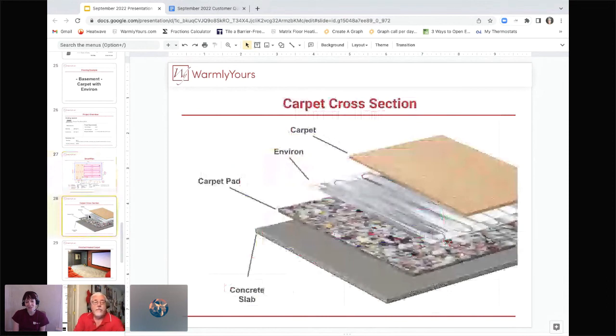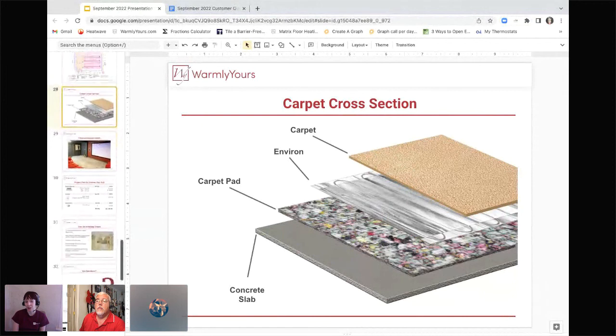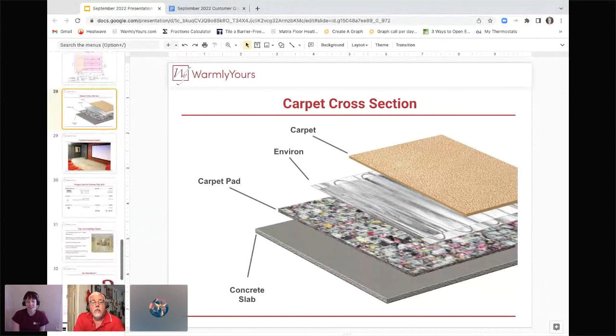Since we're doing carpet and using a carpet pad, we are forgoing the Cerazorb — the carpet pad itself serves as the thermal break. You would just lay the carpet pad directly onto the slab, then place the Environ between the pad and the carpet. That is a question we get a lot — it does feel like the Environ is very close to the surface, but that's what you want to do to make sure there's enough thermal break between the slab and the heat, and that everything heats up and comes to temperature properly.